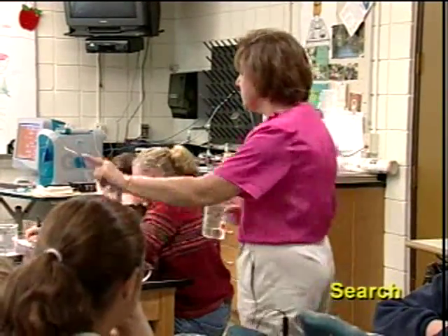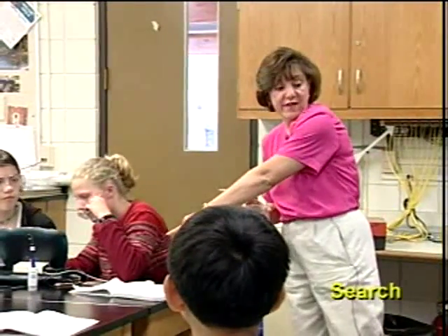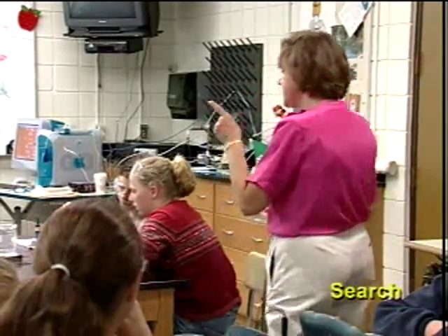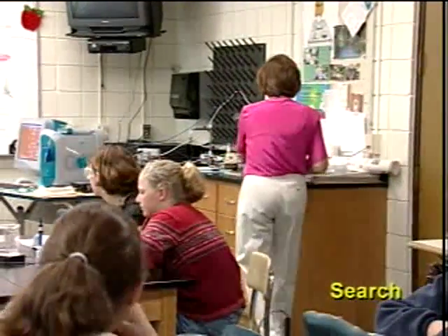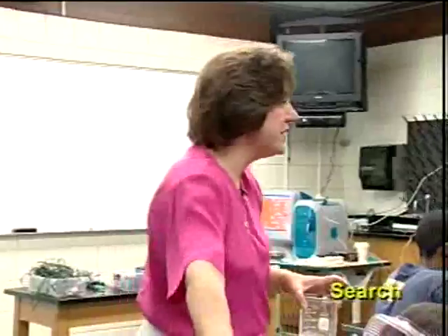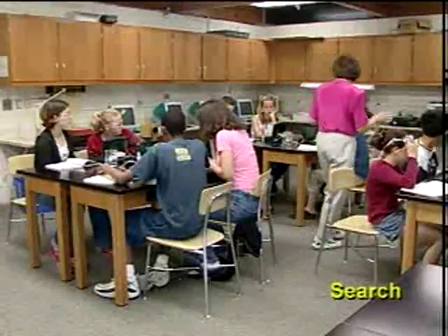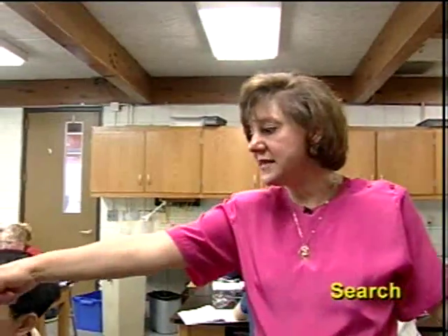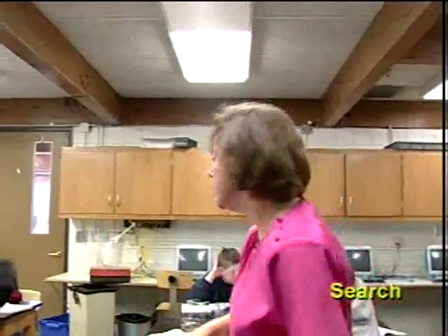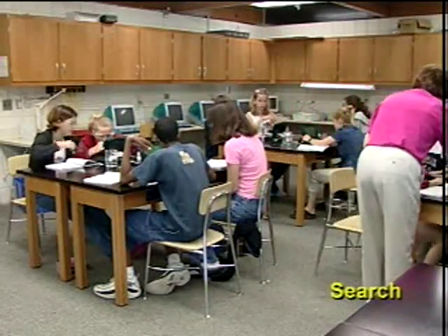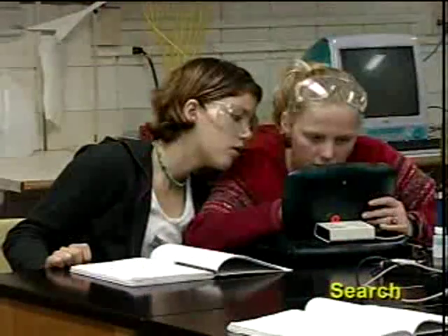Now, when you are done calibrating for the pH, you don't shut out of the program, because what you'll do is switch with this group, and then they'll have the pH of 10, and you'll have the pH of 4, okay? The reason I only set up 2 of them is so that we don't have the small beakers out and possibly get them with any of our equipment or with the tablets, and so we don't spill it. After the teacher gives the students directions, they work in small groups to calibrate their pH probes with Apple eMates. Since they will use these instruments to gather data from the stream, the students are engaged in the search stage of information processing.